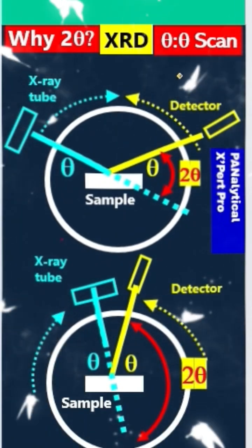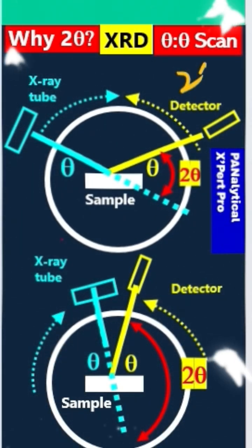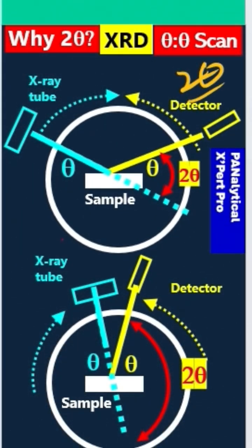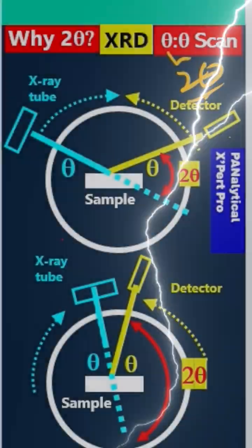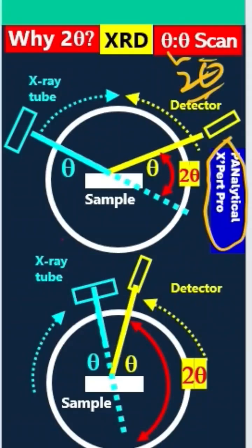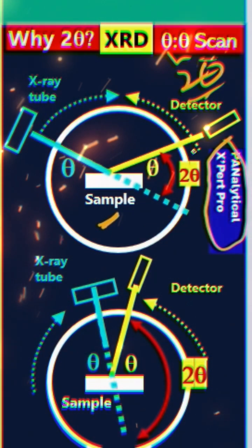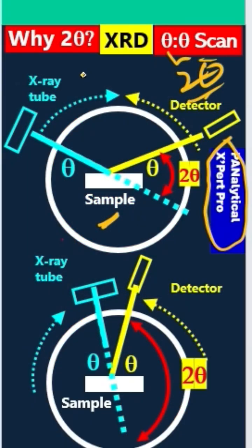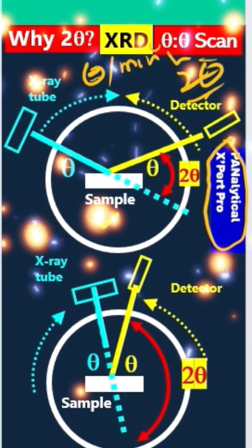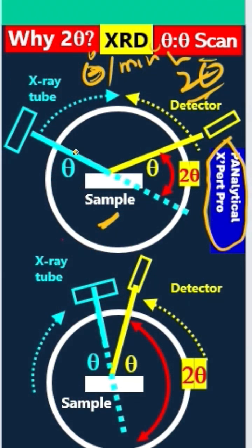Let's discuss why we have two-theta in an XRD pattern in a theta-versus-theta scan. This is the kind of XRD machine that uses this arrangement. In this case, the sample is stationary, but we rotate the X-ray tube as well as the detector at the same theta per minute.